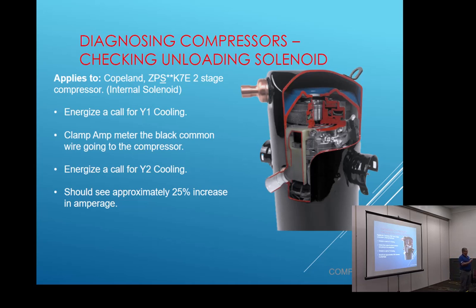Get another one, because I've only seen maybe one where the solenoid was bad inside the compressor and the compressor had to be replaced. Maybe 2. It just doesn't happen, okay? So more than likely, it's the rectifier. But just because on the side of the compressor right here, in that plug, okay? So get a new harness with the plug on it and replace it. That'll probably take care of it. If that doesn't fix it, well, then you got to replace the compressor.